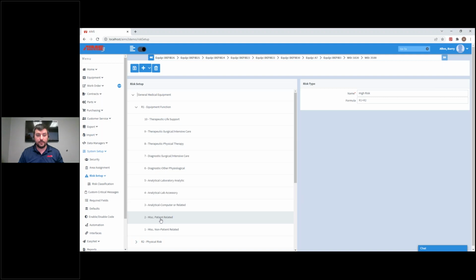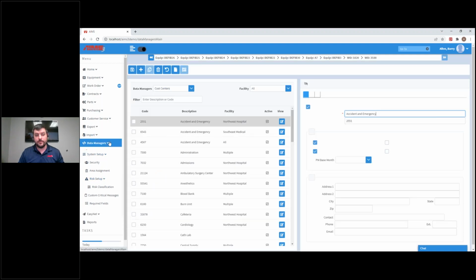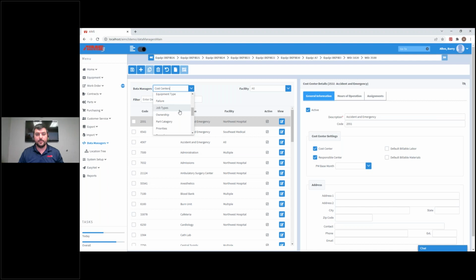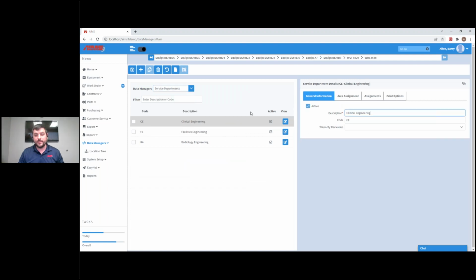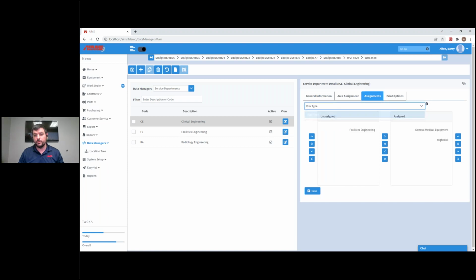Once all these come in, then over at the service department level, which is our main split we're talking about here, you can limit what risks each one sees. So for my clinical engineering department, when I come over to risk type, I can determine which of those risks this group of technicians has access to. They won't even see the other ones. When they're on an equipment record or a work order and they're trying to look through risk, they're not even going to see those in the database. That's how separate we keep this. Same thing, if I'm a facilities tech, I'm only going to see my one list of facilities risks. I'm not going to see the other ones.